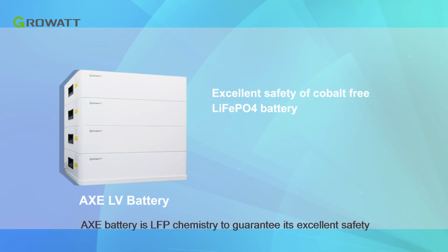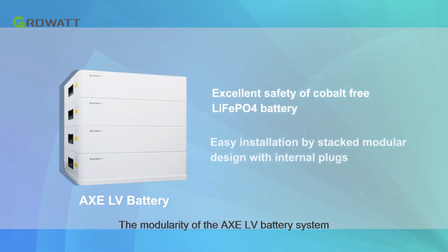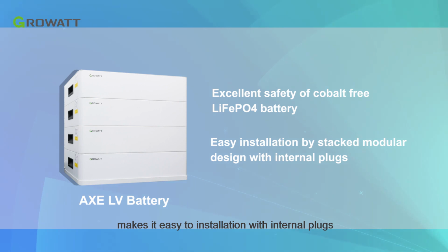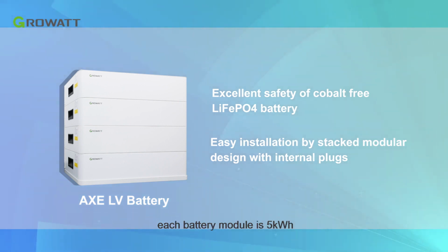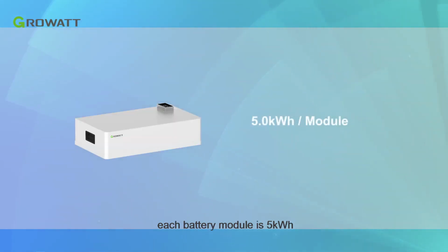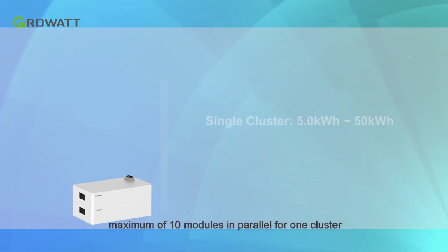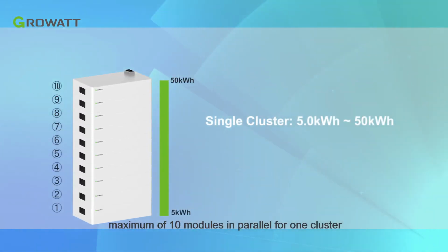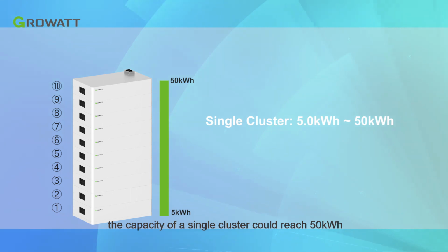The AXE battery is LFP chemistry to guarantee its excellent safety. The modularity of the AXE LV battery system makes it easy to install with internal plugs. Each battery module is 5 kWh. A maximum of 10 modules can be in parallel for one cluster. The capacity of a single cluster can reach 50 kWh.